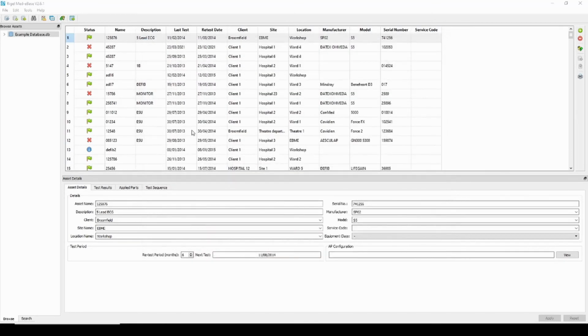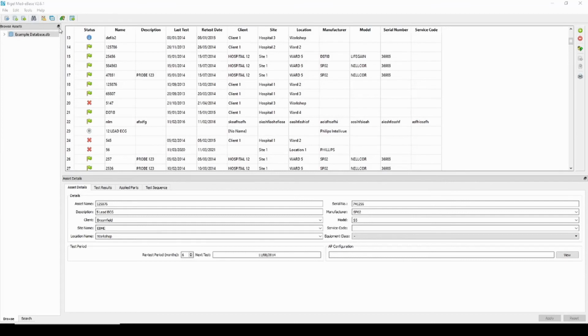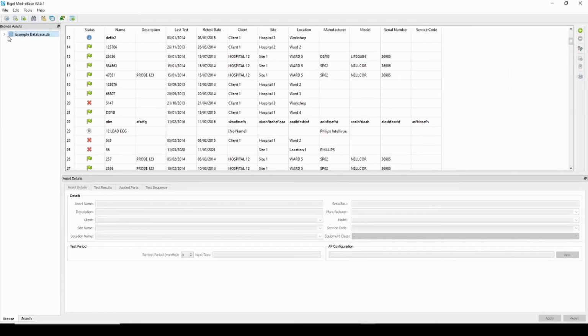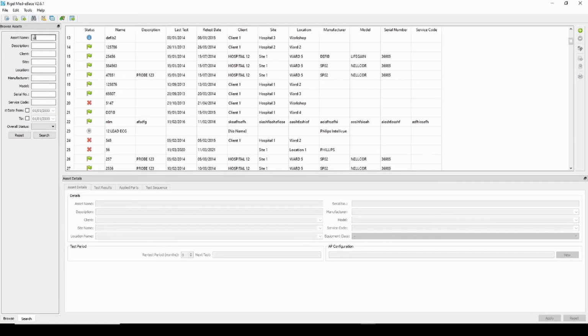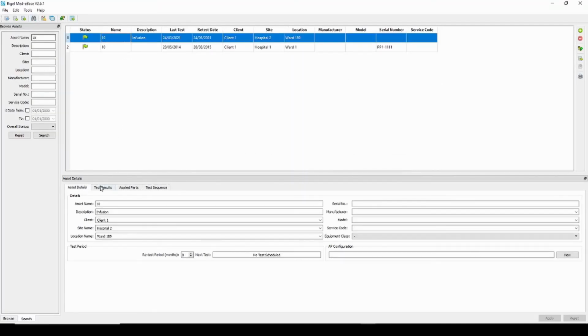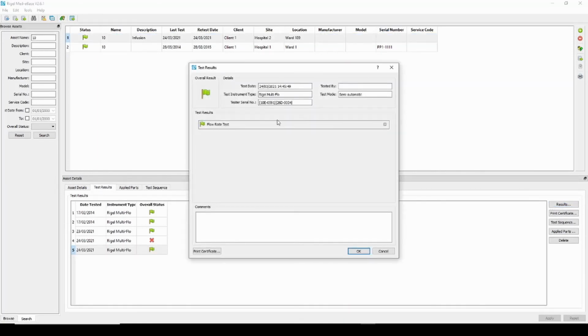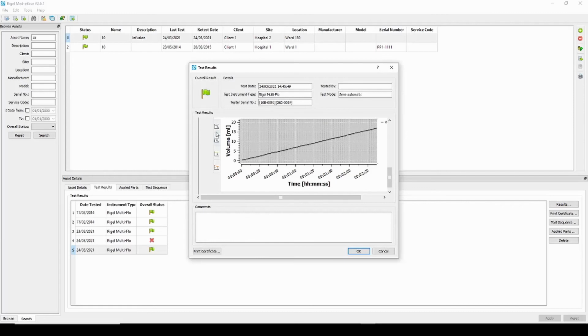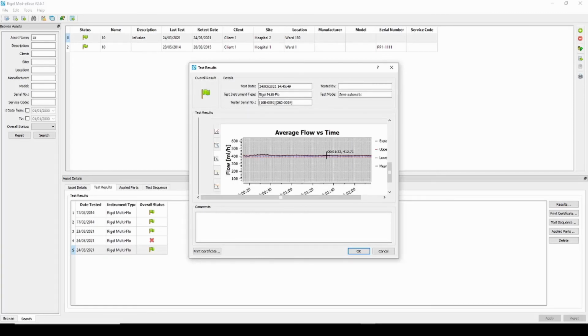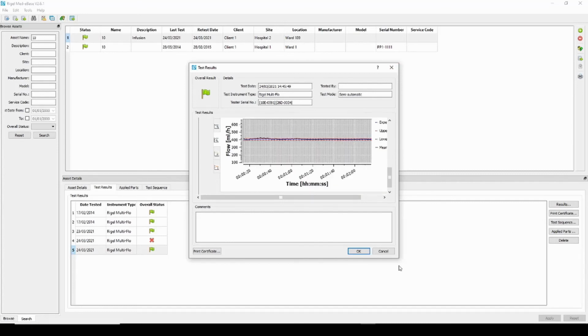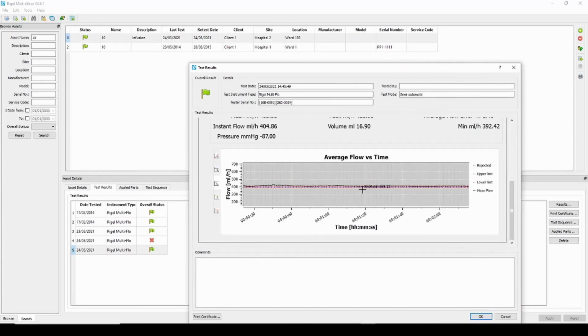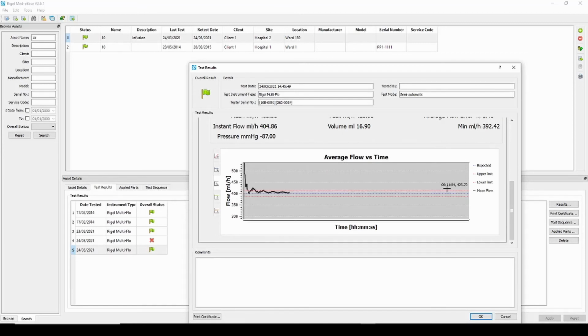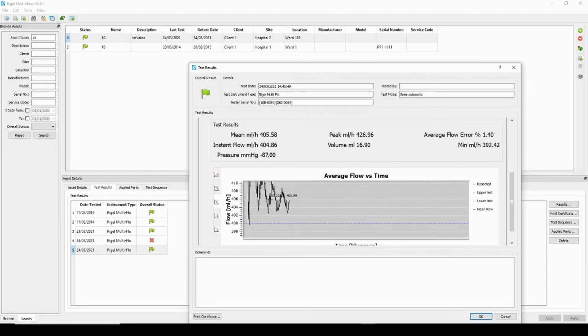And now that data is recorded, we can have a look in the results under the asset ID number. So if we go to search using Med-eBase, top one there, so it's saved under asset ID 10 for the last test that was done, which was this one. You can view the results and see all those different waveforms that were saved under that asset ID. So we're looking at the average flow rate. We can zoom in and take a real good look at the data that we've got. So we can zoom in there a little bit better and see the average flow over time. If we want to have a look at a bit more in-depth analysis.